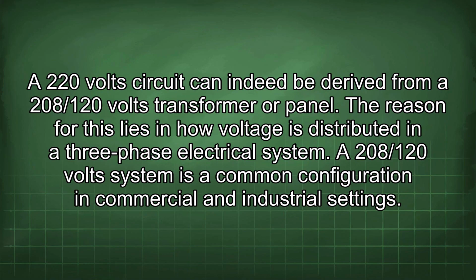A 220-volt circuit can indeed be derived from a 208/120 volts transformer or panel. The reason for this lies in how voltage is distributed in a three-phase electrical system. A 208/120 volt system is a common configuration in commercial and industrial settings.